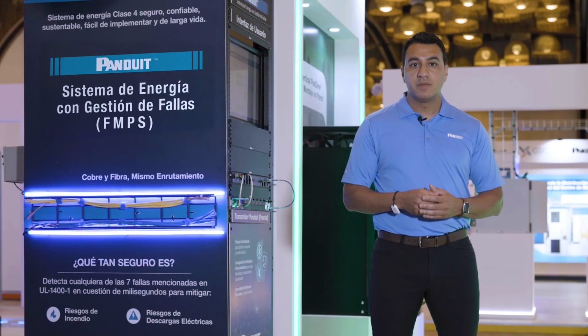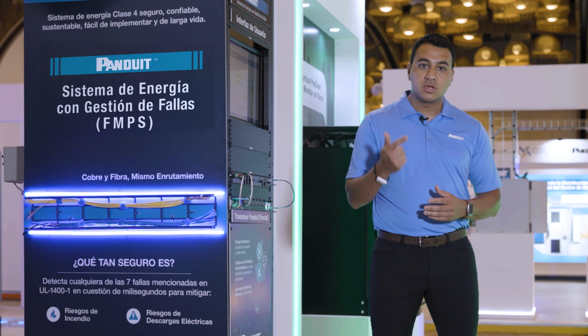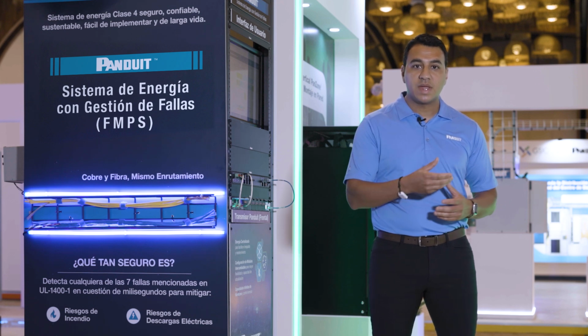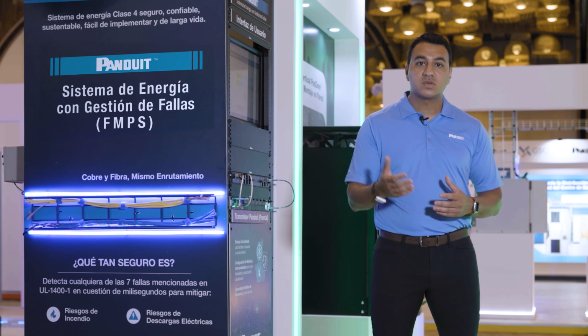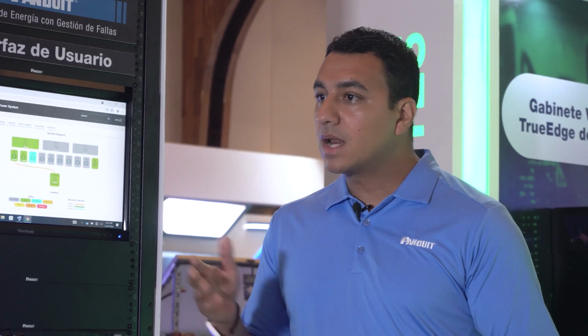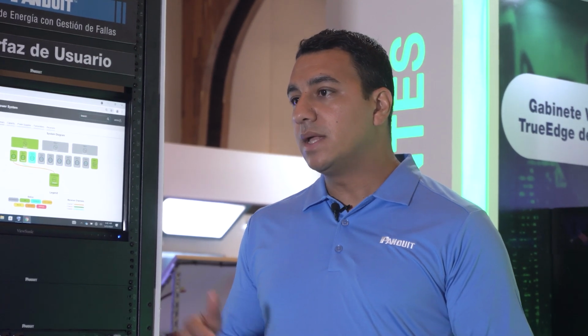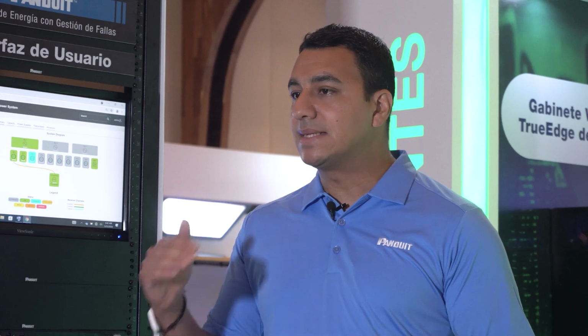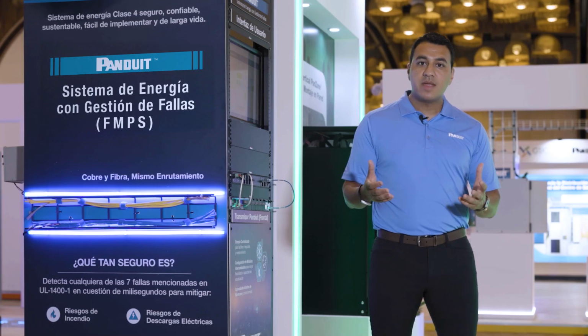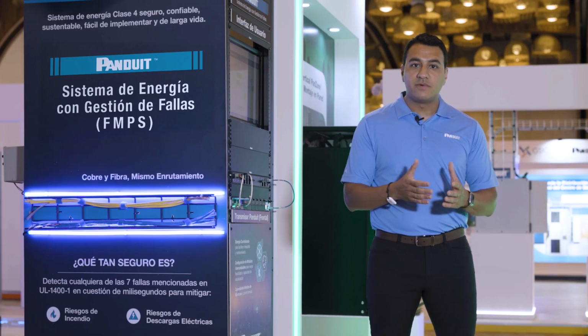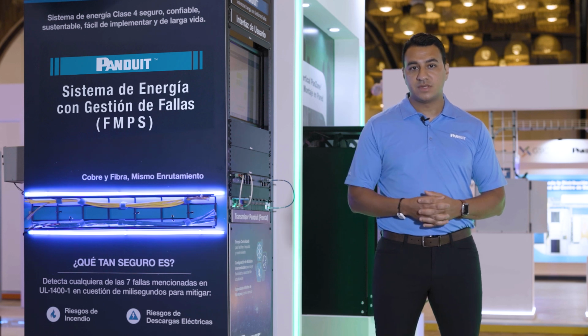It's great for what we use today, but it's not safe because it can start a fire and it could shock someone if they touch it. And that's why we have to run it in conduit, and that's why you have an electrician install it. Class 2, you may be familiar with. It's limited to 100 watts and 60 volts. That's great because this limitation allows a low voltage installer to install the cable for this technology.